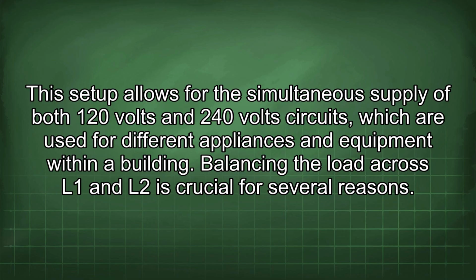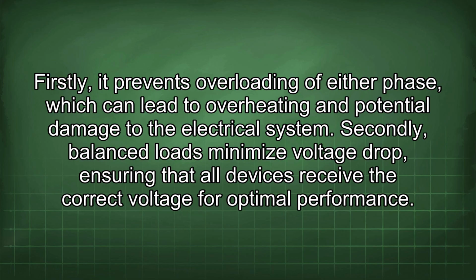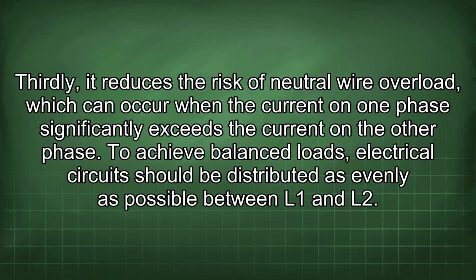This setup allows for the simultaneous supply of both 120 volts and 240 volts circuits, which are used for different appliances and equipment within a building. Balancing the load across L1 and L2 is crucial for several reasons. Firstly, it prevents overloading of either phase, which can lead to overheating and potential damage to the electrical system. Secondly, balanced loads minimize voltage drop, ensuring that all devices receive the correct voltage for optimal performance. Thirdly, it reduces the risk of neutral wire overload, which can occur when the current on one phase significantly exceeds the current on the other phase.